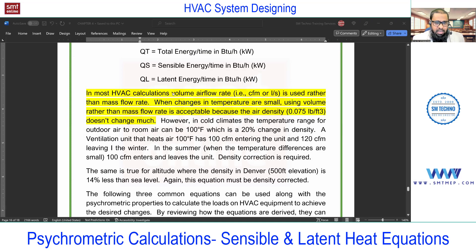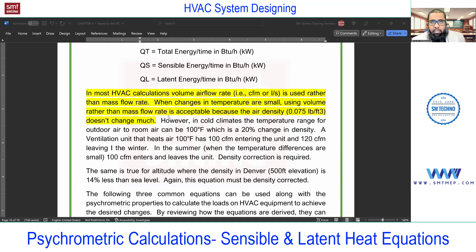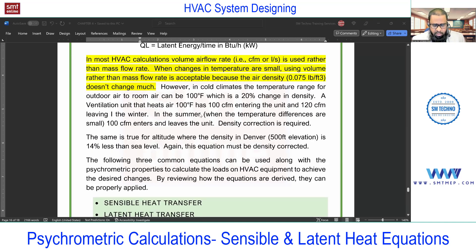In most HVAC calculations, volume flow rate is used rather than mass flow rate. We are using CFM — volume flow rate — instead of mass flow rate. When changes in temperature are small, using volume flow rate rather than mass flow rate is acceptable, because the air density doesn't change much. In cases of very high temperature differences, like minus 20 or minus 40 in Canada or similar locations, that is a special case. But in India, the Gulf, and many Western countries, the temperature difference is relatively small, so we assume density change is very little — that is why we consider volume flow rate instead of mass flow rate.